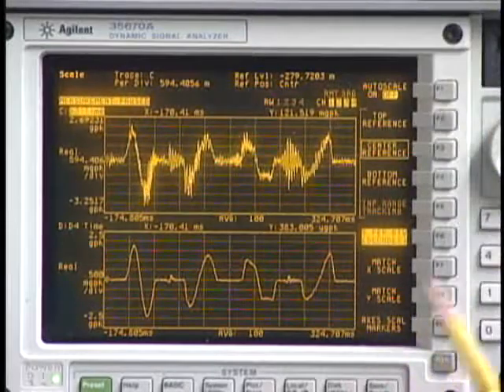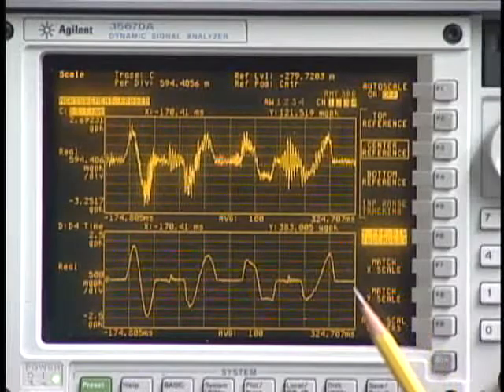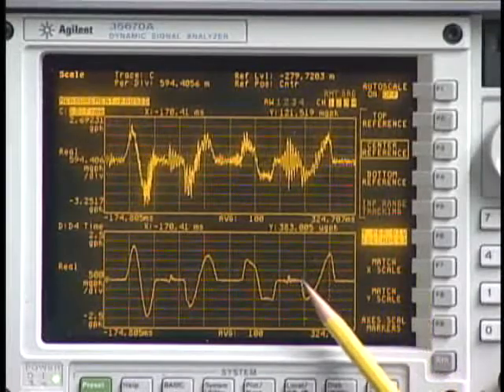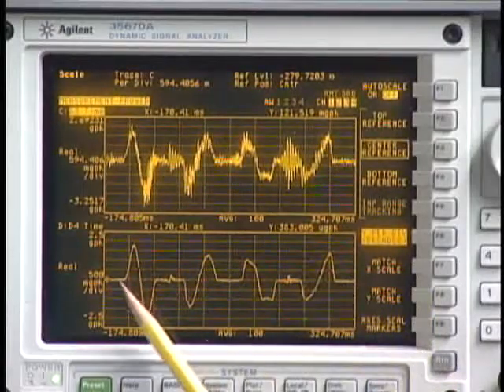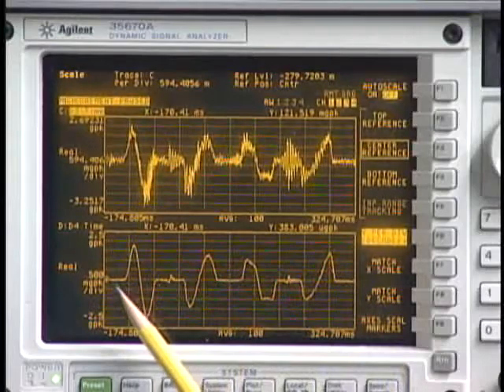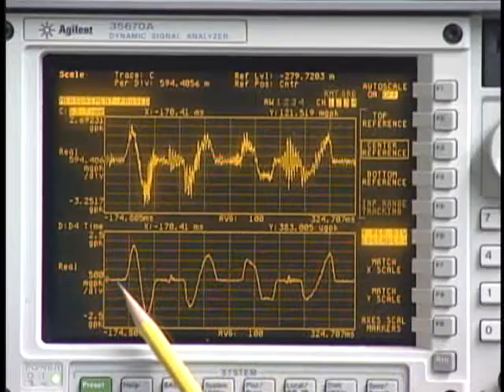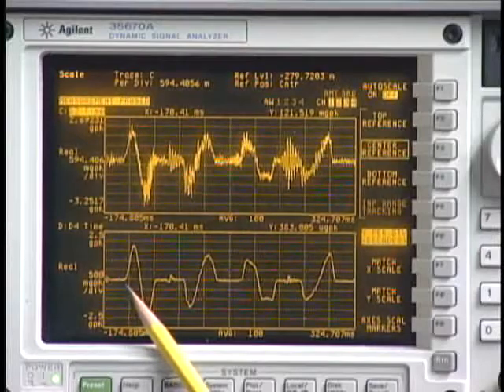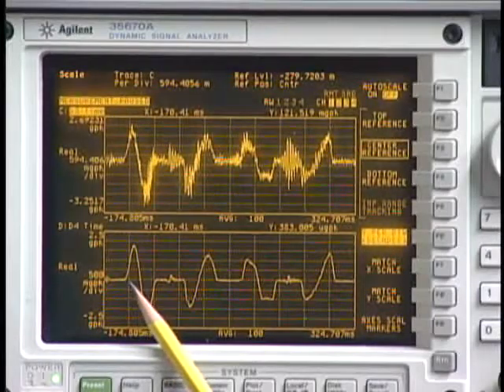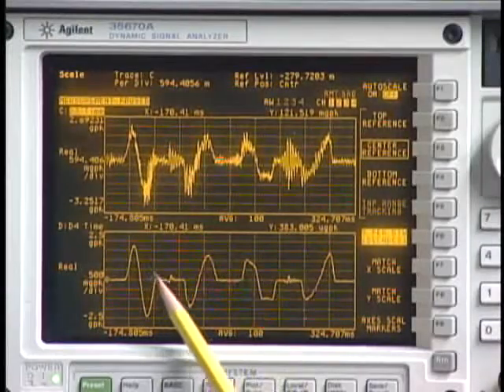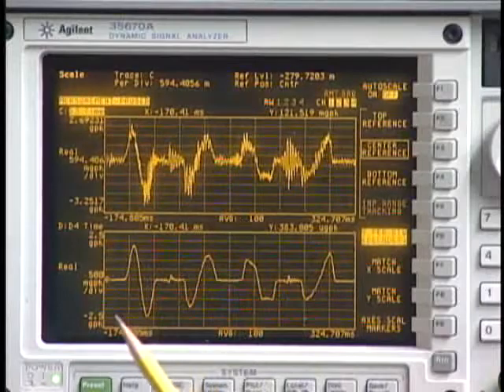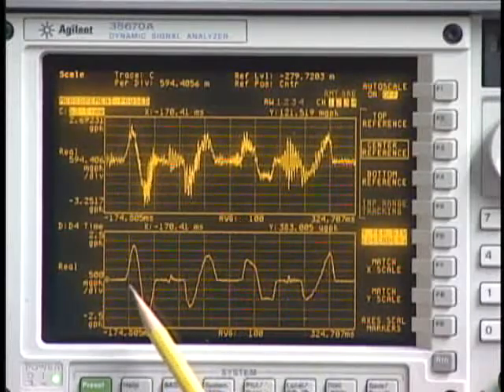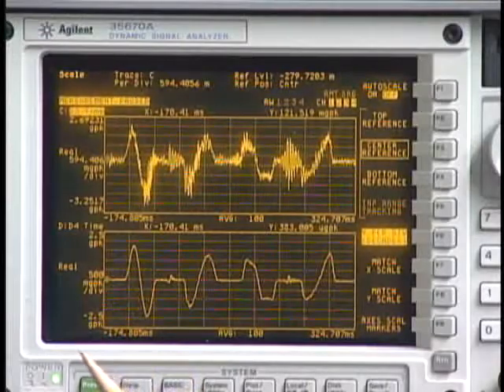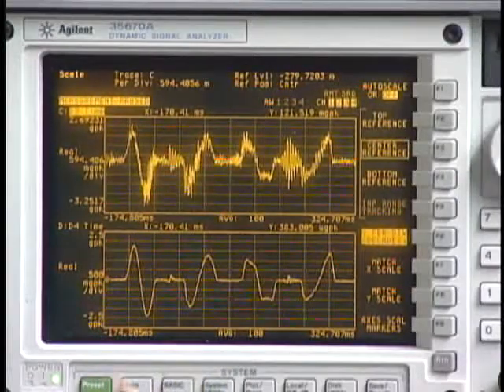Now, we can see better what we have for acceleration by using a filter. And I've applied a filter to this system, and we can move over and show you that filter box in a moment, but the result of the filtering is to remove the high frequency information. And this is the same function down here as here, but it's been run through what's called a low-pass filter. And that's taken out all the frequencies above. I set it to about 110 hertz. This is running at 2 hertz as the fundamental frequency, 120 revolutions per minute. So I've taken out everything from 55 times that up.